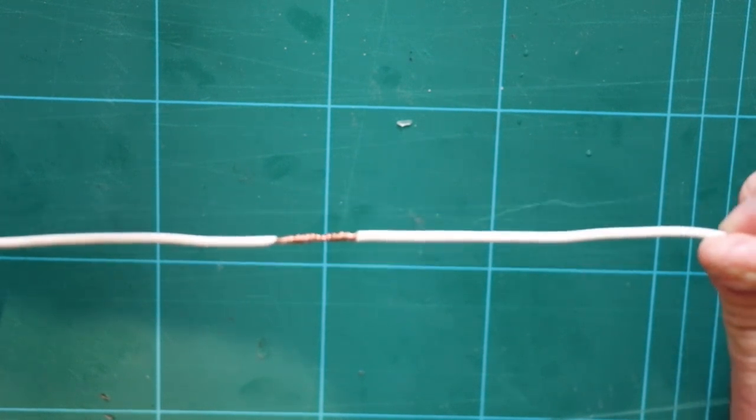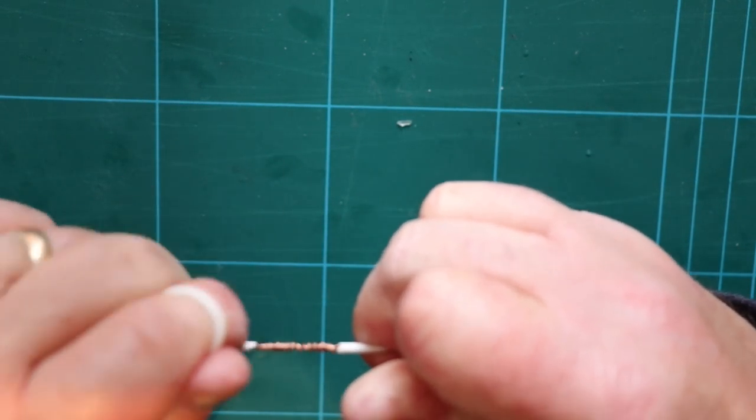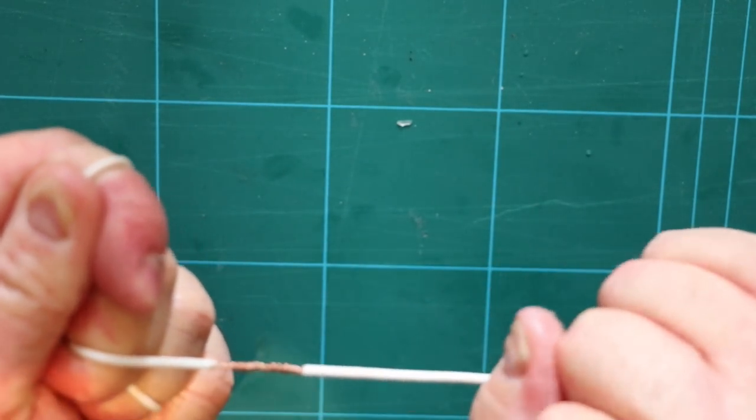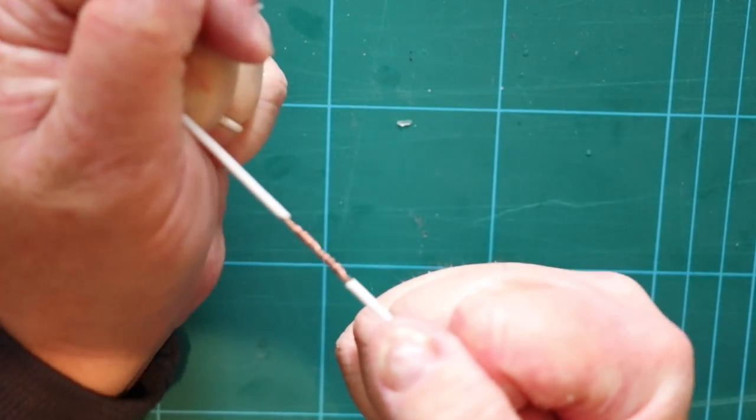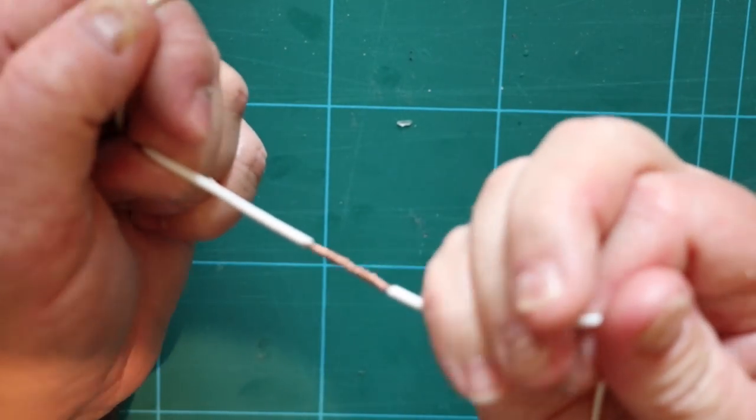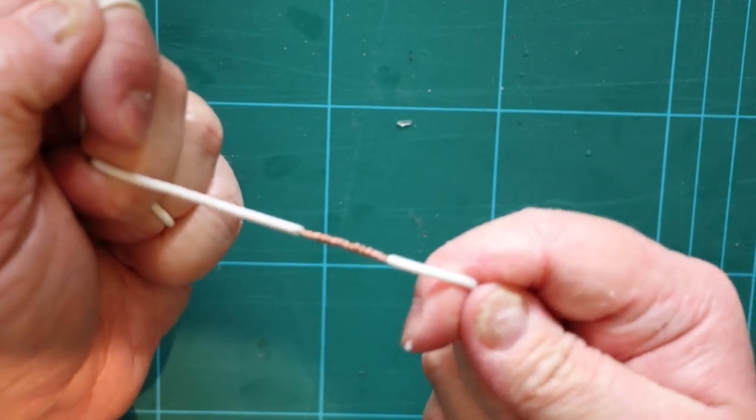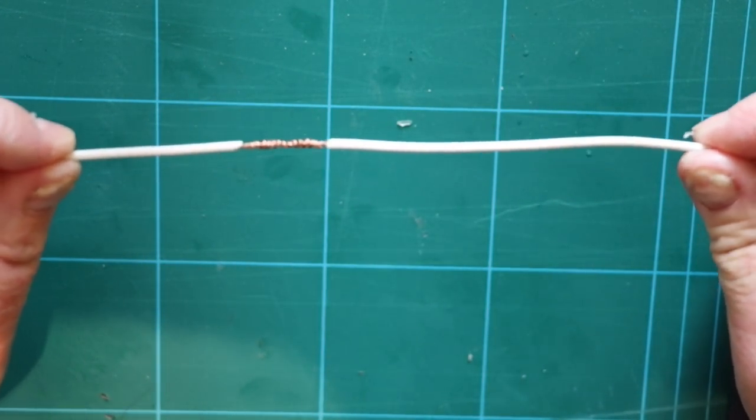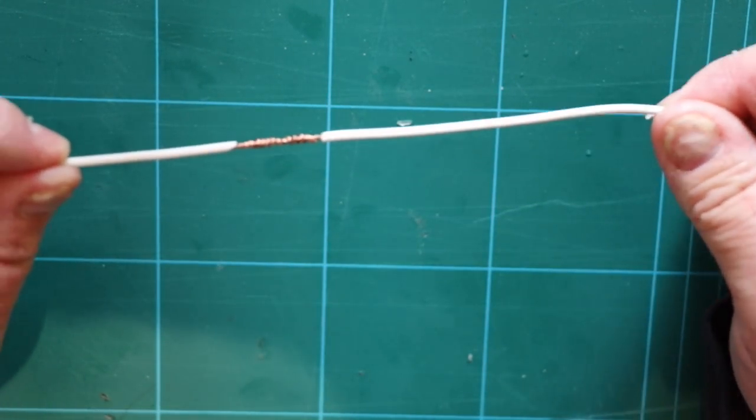It is unbelievably strong. If I now try and pull this apart, believe me I am trying here, I cannot pull that apart. Because the fact is this: if you pull it, it actually makes that tighter. So that's a Western Union splice. You can see it's really, really effective. All we need to do now is put some tape around that, and that is an excellent temporary join.